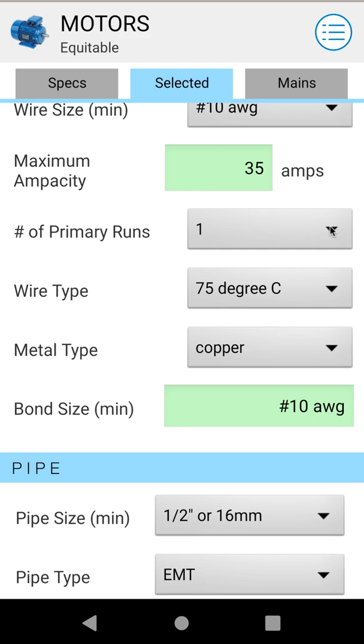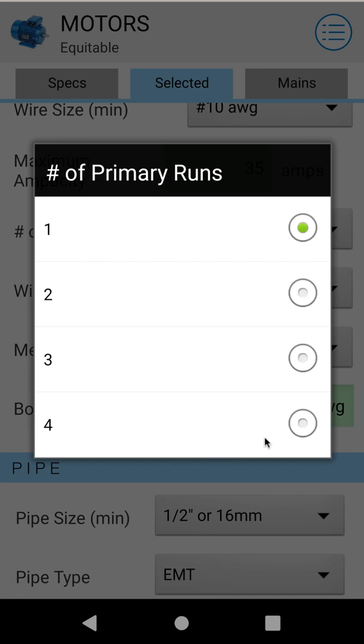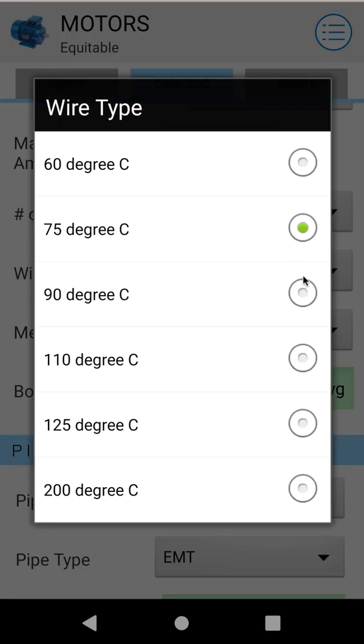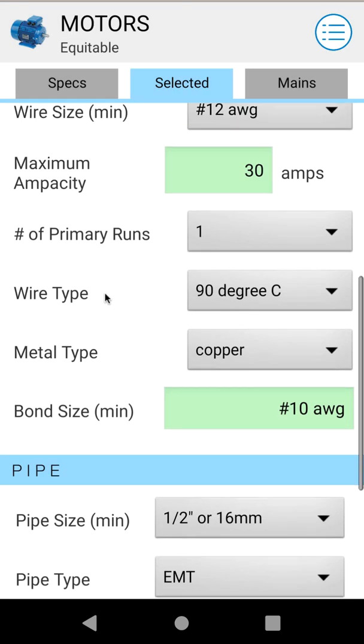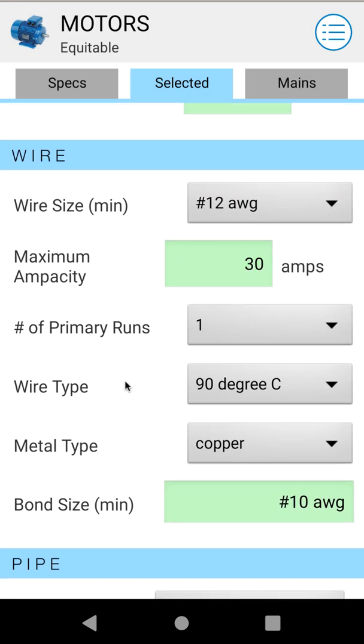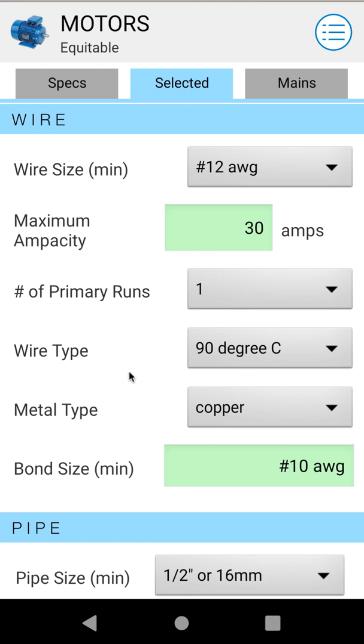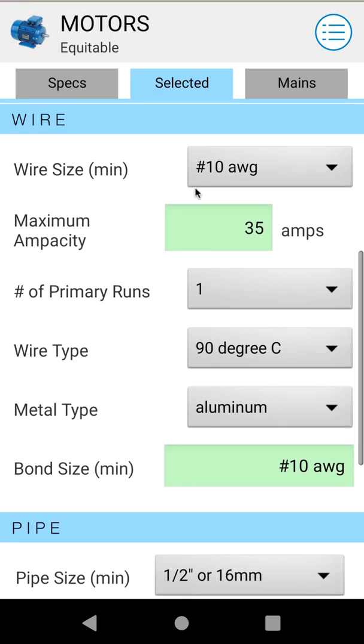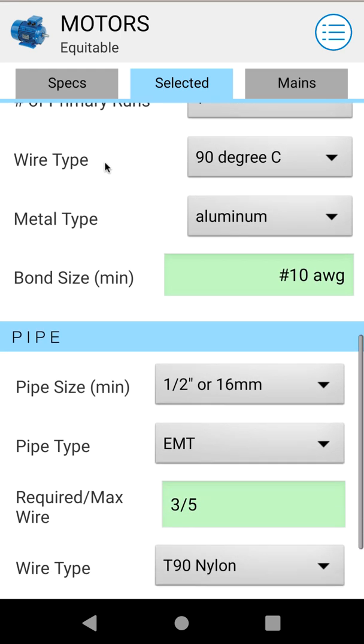Number of runs — you can go with a single primary run, or if you're calculating a larger motor you can go up to two, three, or four parallel runs. Next you can choose your wire type, so you can go up to a 90 degree wire such as T-90. This will also affect your allowable ampacity and your calculated wire size. You can also choose from copper or aluminum feeders, which will again affect your calculated wire size and ampacity.